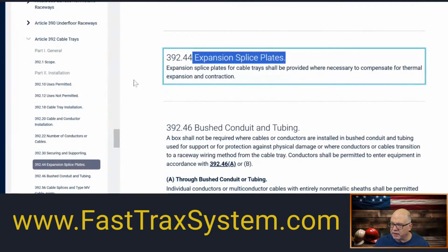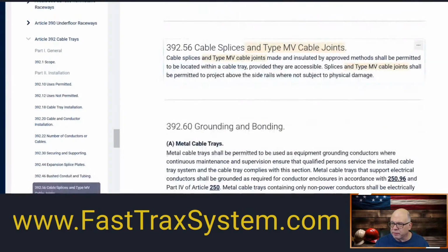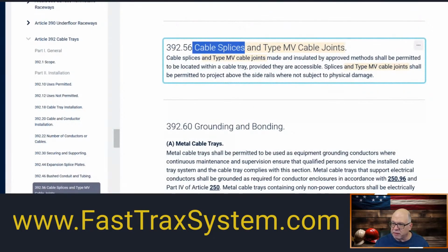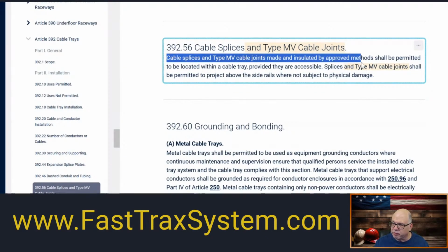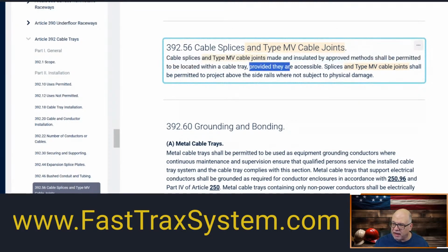Expansion plates, splice plates. All right, well, splice is in there, but you notice it's really not dealing about splices and joints itself, so obviously that didn't help you. We're skipping down. Boom, right here. Cable splices and type MV cable joints. Okay. And I also can tell you, I see the word approved, and that was in our question, so I know I'm in the right place. So cable splices and type MV cable joints made and insulated by approved methods shall be permitted to be located within a cable tray, provided they are accessible. Okay? And then everything else is just continuing on with the same verbiage as our question was. But the key is accessible.